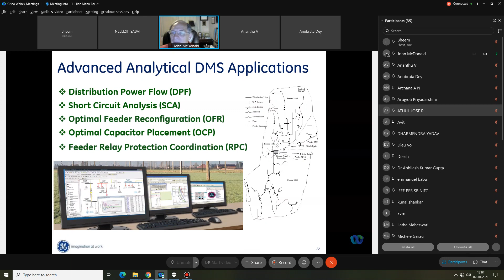The second group is what we call on-demand analytical applications, used for specific tasks like short circuit studies, optimal feeder reconfiguration after an outage, and the optimum location to install capacitors on distribution feeders. The distribution power flow is really today both a real-time and an analytical application. It gives us the ability to model the distribution system on a full three-phase unbalanced basis and simulate the impact of different actions. The third group is ancillary or additional applications that the utility wants to run.